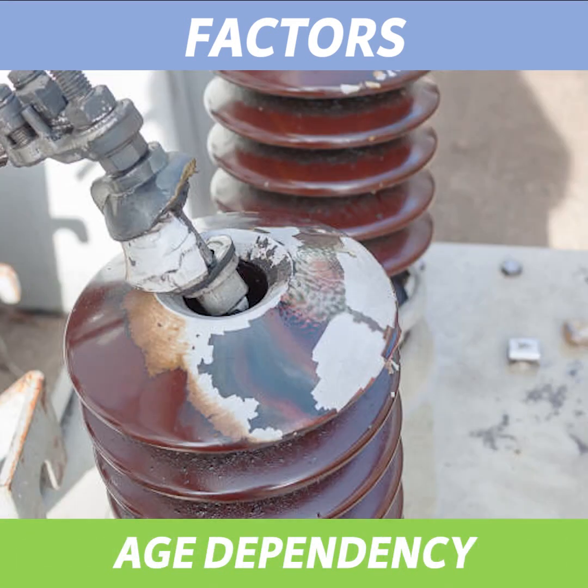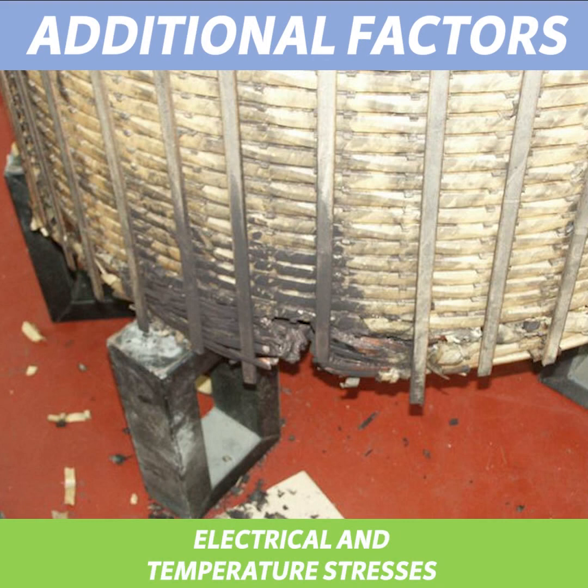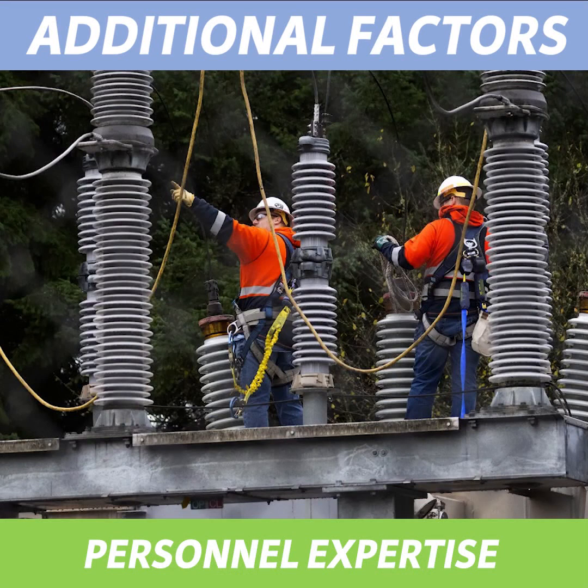Age dependency. Older bushings are more prone to failure compared to new bushings, but there have been many incidents over time, leading to increased risks of failure or breakdown. New transformers can also be prone to failures in craftsmanship and materials. Additional factors. Electrical and temperature stresses to which the bushings are subjected, such as voltage levels, overloads, short circuits, etc. Higher electrical and thermal stresses can accelerate insulation deterioration and increase the risk of failures. Personnel expertise. The expertise of personnel involved in maintenance, testing and decision-making to mitigate risks effectively.